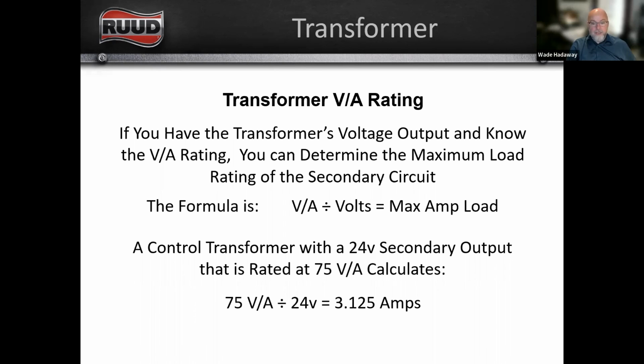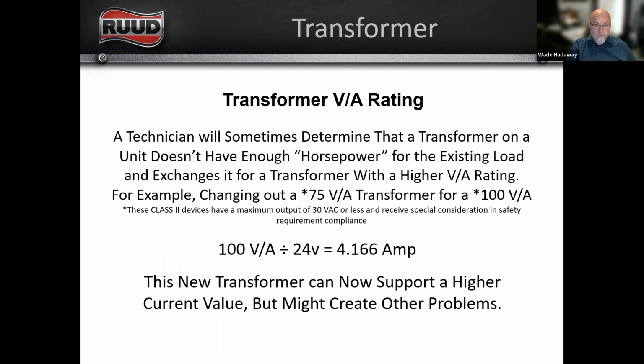Say you upgrade the transformer, then you put a 5 amp fuse in that board, but the board is only rated for 3 amps. Now you're going to kill that board instead of blowing the fuse or killing the transformer. I'm just throwing out broad general terms, but a 100 VA transformer divided by 24 volts can handle 4.166 amps. So you would not want to put a 5 amp fuse in there.